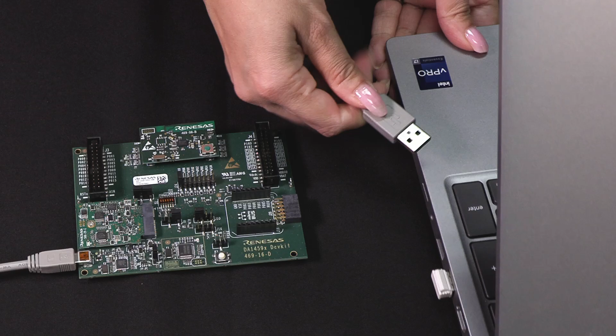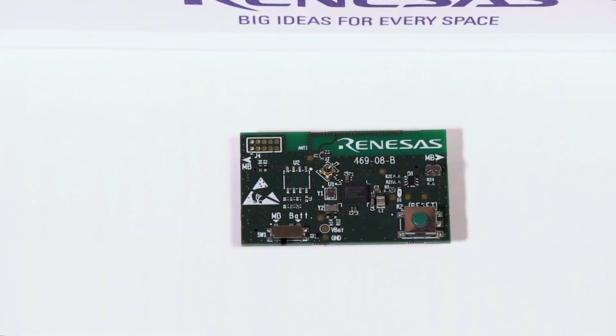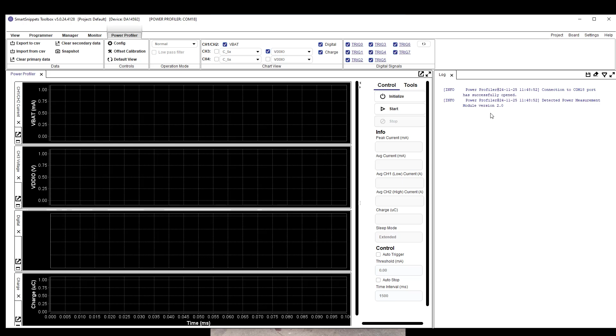The steps to calibrate are: connect the motherboard to the PC, remove the daughter board so that it does not dissipate any power. Alternatively, power off the daughter board via the daughter board power switch. The motherboard should still be powered on. Press the Initialize button from the control toolbar of the Power Profiler tool to detect the PMM version. Next, press the Offset Calibration button from the Controls group of the ribbon found up here. Data will be collected for about 10 seconds and then will automatically stop.